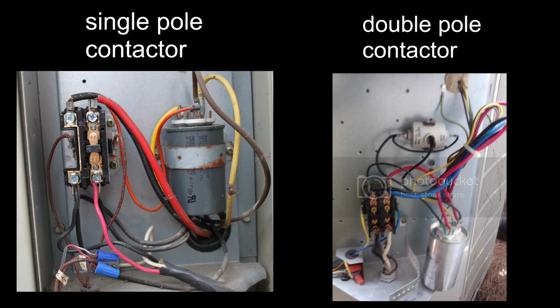But it's basically a single pole, meaning it only has one pole on the right side. And then on the other side where it says double pole contactor, basically it's the same thing as a single pole, except it has two contacts. The reason I like using dual pole is because it has two contacts, and it allows that contactor to last longer. That means it has two poles of contact instead of one. That means I can get almost double the life out of that one, as long as it's maintained and taken care of properly.